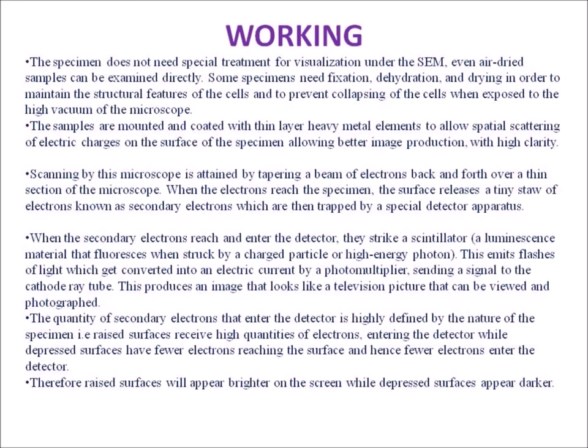This slide explains the working of the scanning electron microscope. The specimen does not need special treatment for visualization under the SEM — even air-dried samples can be examined directly. However, for histological and microorganism specimens, fixation, dehydration, and drying are needed in order to maintain structural features of the cell and to prevent collapsing of the cell when exposed to the high vacuum of the microscope. The samples are then mounted and coated with a thin layer of heavy metal element to allow spatial scattering of electric charges on the surface of the specimen, allowing better image clarity.